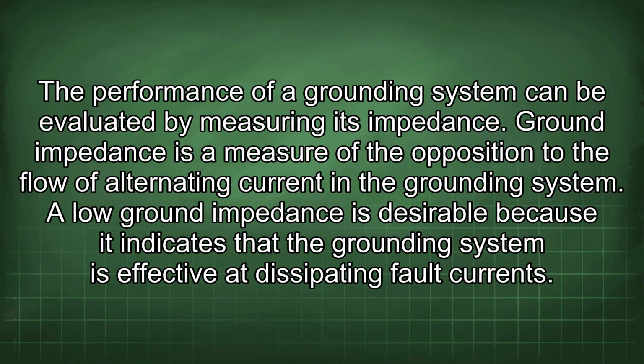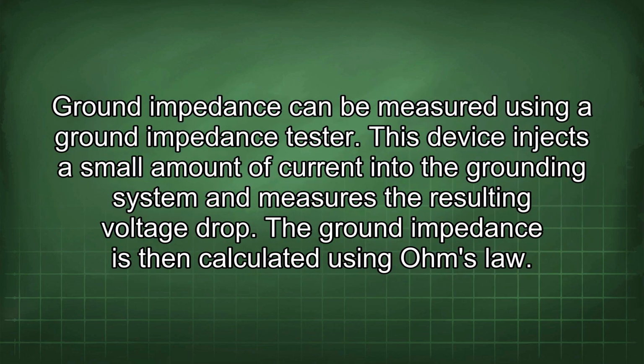The performance of a grounding system can be evaluated by measuring its impedance. Ground impedance is a measure of the opposition to the flow of alternating current in the grounding system. A low ground impedance is desirable because it indicates that the grounding system is effective at dissipating fault current. Ground impedance can be measured using a ground impedance tester. This device injects a small amount of current into the grounding system and measures the resulting voltage drop. The ground impedance is then calculated using Ohm's law.